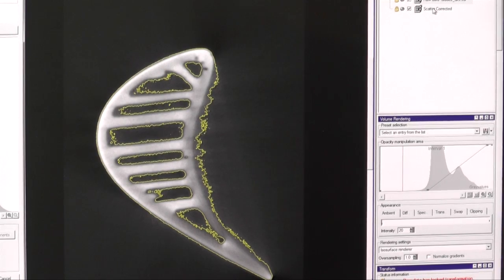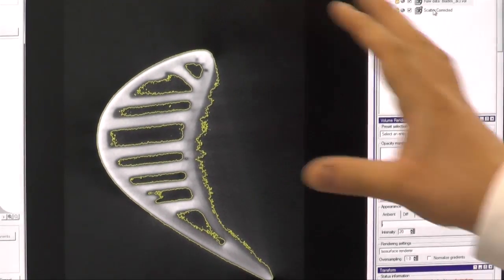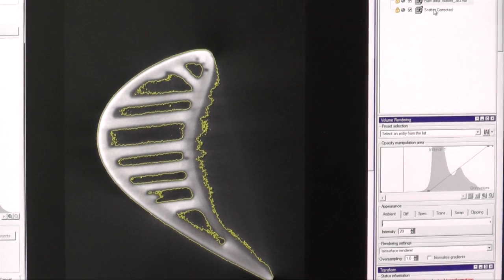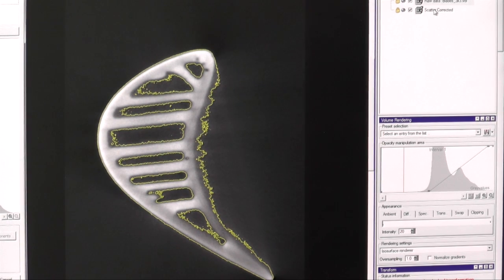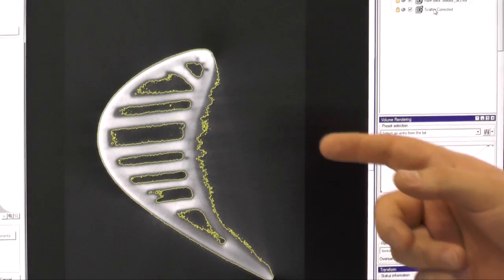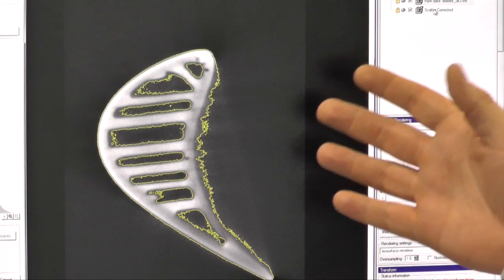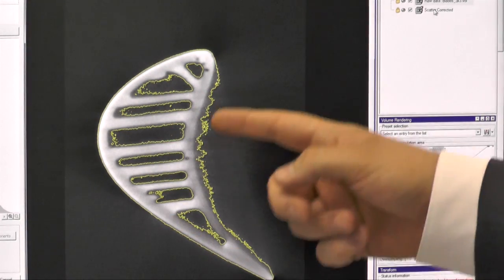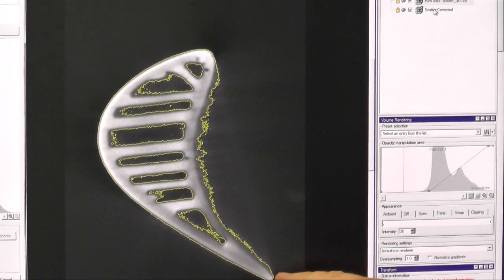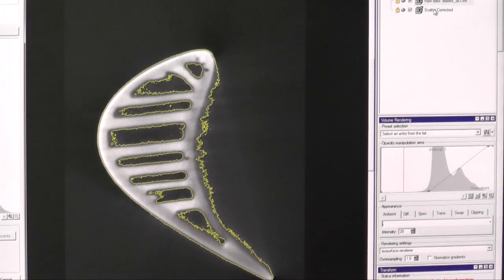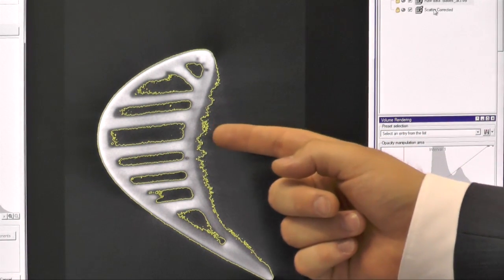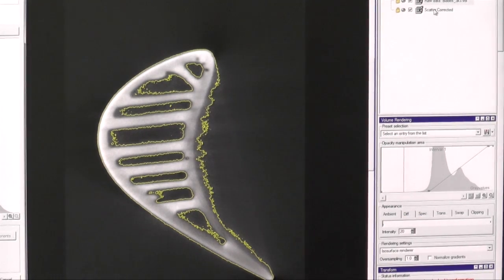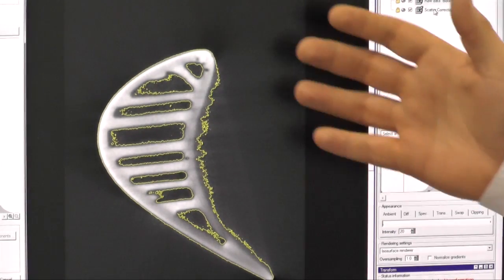Here at the visualization of the CT scan, I would like to make a little more obvious what the result of scatter radiation is. We see here the result of a standard cone beam CT using a 40 by 40 centimeter detector without ScatterCorrect — a conventional CT scan. Using automatic surface detection, you can see the surface of the part is not really detected precisely; the surface appears to be in the air as a result of scatter radiation.